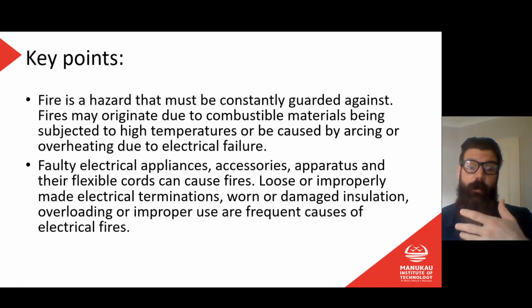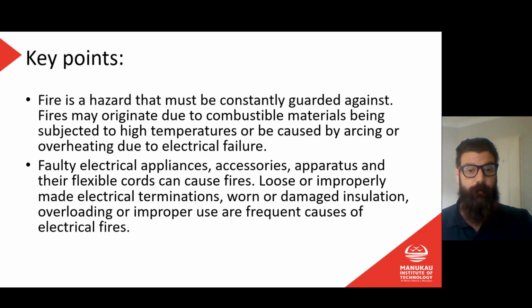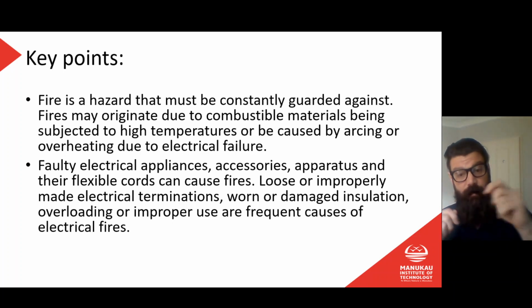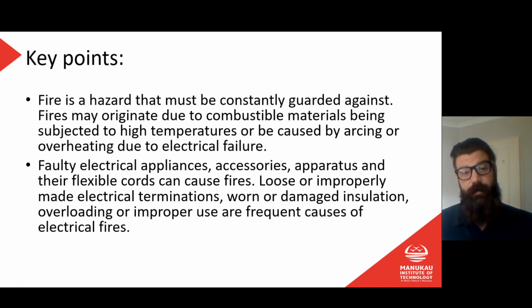When we're talking about overloading on a multi-box, that's just the amount of current that we're pumping through that multi-box. If you think about the fact that a single outlet on the wall is good for 10 amps, and then I plug in a multi-box with 4 plugs on it, and I can plug 4 appliances in there, I could easily draw much more than 10 amps, and that's going to cause heat in that circuit, because nothing on that circuit is rated for greater than 10 amps. And that's going to cause us a problem as well. It could potentially lead to a fire.